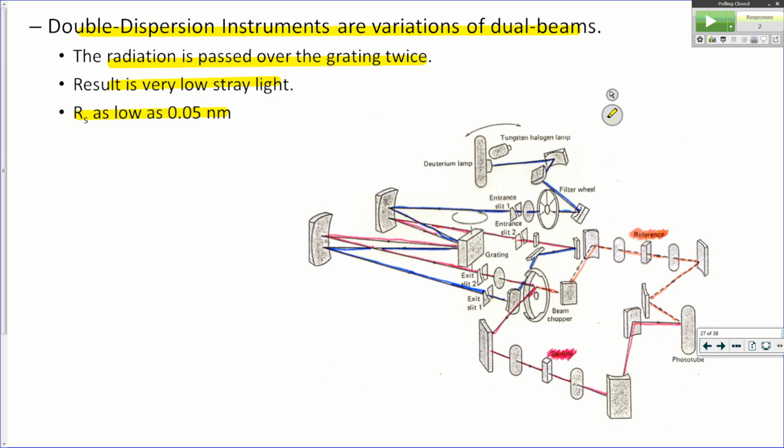So you've got a source with either a tungsten lamp or deuterium, and it's going to switch back and forth. And that grinding sound that we hear with the Shimadzu instrument is actually the source switching the mirror for the source. When it stops, when it scans, the light goes through and strikes a series of filter wheels, and that way it's going to have cut off and cut on filters to isolate a certain region so you don't have order effects from the monochromator.